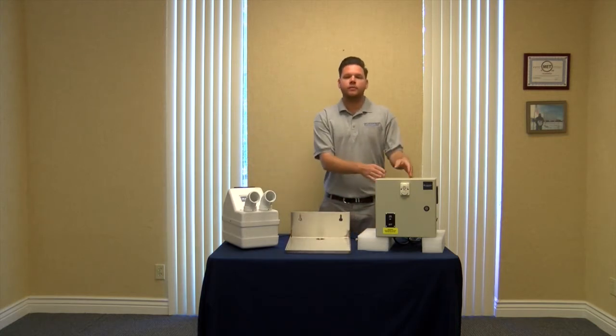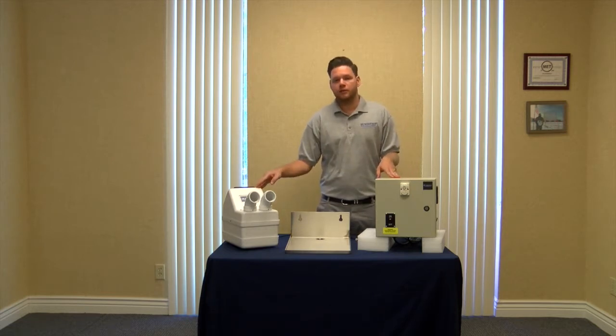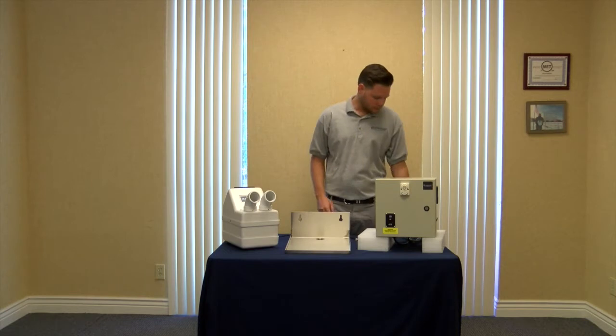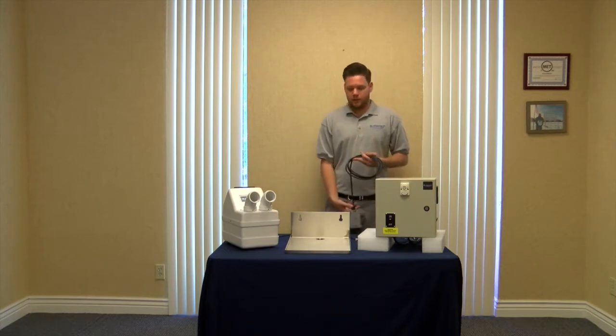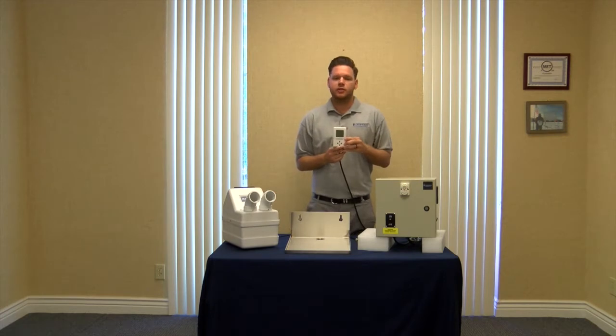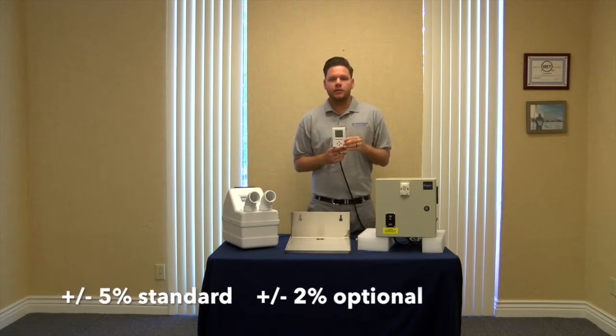When mounting your unit mount control panel, you have 10 feet of distance from the control panel harness that plugs up to the humidifier. If you need to go any longer than that, you might need to gauge up and use a junction box. Also included is our Humidifirst digital humidistat. When mounting the digital humidistat, you want to make sure to also mount it in a centralized location, not directly in front of the humidifier. If the mist blows directly onto the humidistat, you will get false readings.